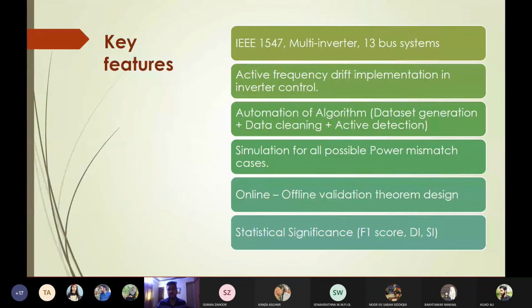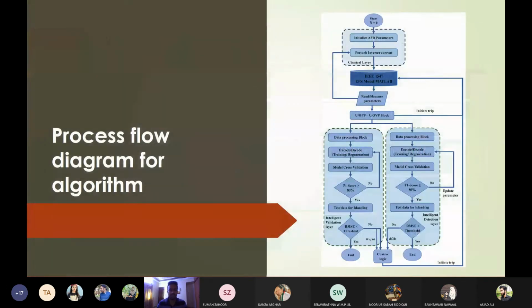Since it was a hybrid system, I applied active methods along with it — you may not be familiar with these, but don't worry. I implemented active frequency drift in the inverter control, changing the inverter control slightly, and deployed both an active method and a passive detection method. I simulated all of the power mismatch cases — let me show you the result.